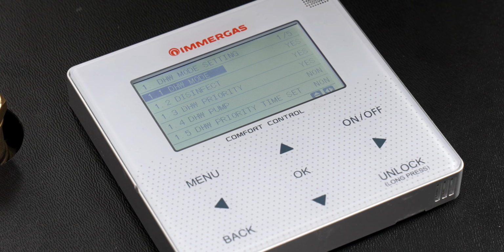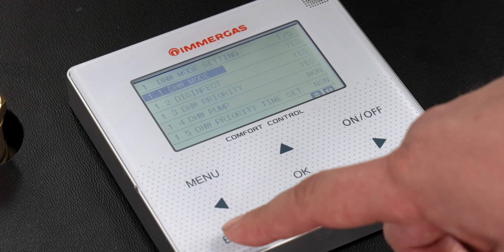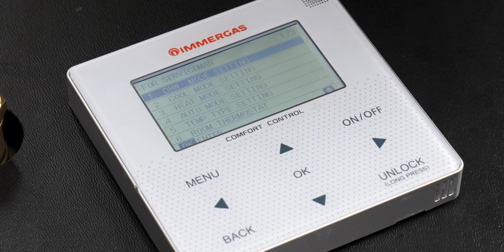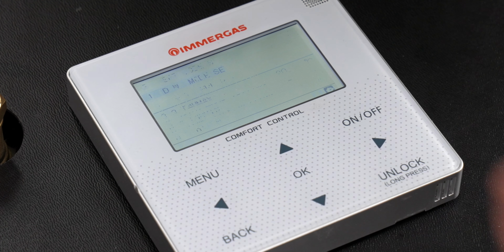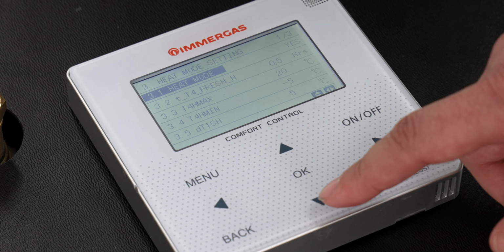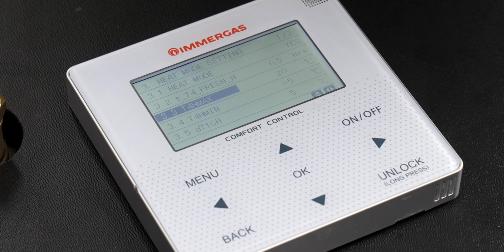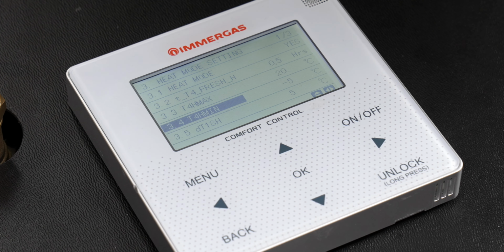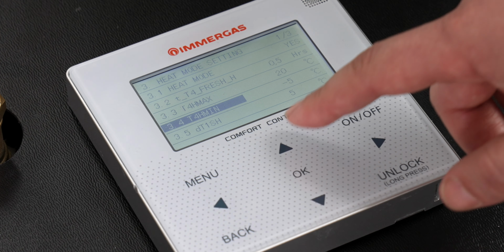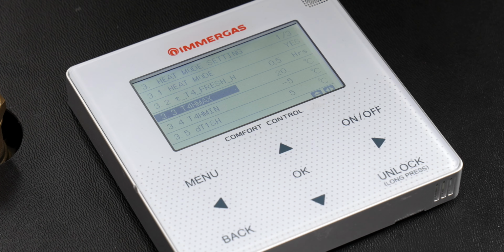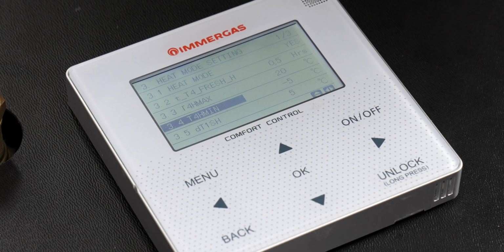and as you can see we've got hot water turned on. So we'll come out of that. The next one you want to make sure is you've got heat mode settings. So you come down to number 3. Now in heat mode settings, down at number 3, you'll see it says 20 degrees, and down at number 4, you'll see it's -5. We advise that you keep the 20 degrees at 20, but the -5 should be conditional to whatever area you're in. So for me in Scotland, sadly, I will always use -5.